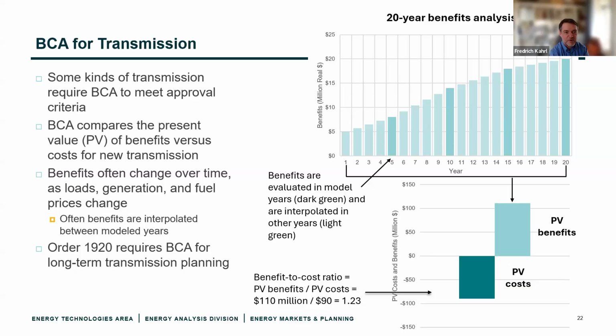Because transmission has such a long lifetime, averaging somewhere between 40 and 60 years, the benefit cost analysis has to have a very long time horizon, usually a minimum of 10 years, but it could be longer, 20 years, maybe even 40 years. On the cost side of the benefit cost analysis, most of the costs of the transmission line are going to be upfront.